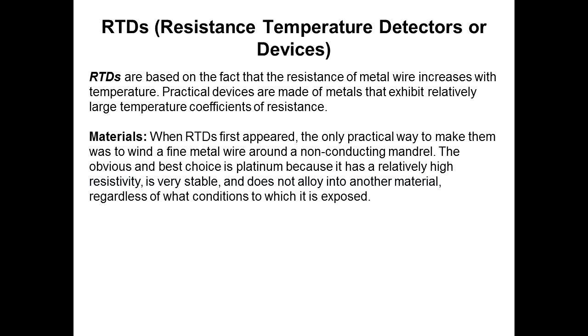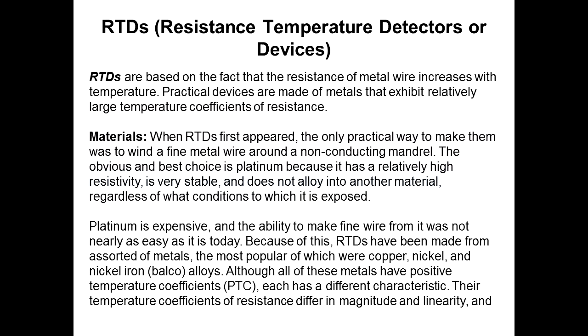This non-conductive mandrel is usually a ceramic or a glass mandrel, so that makes them fragile. Platinum is expensive, and the ability to make fine wire from it was not nearly as easy as it is today. Because of this, RTDs have been made from assorted metals, the most popular of which were copper, nickel, and iron nickel, which was called Balco alloy, which was used in the power industry many years ago.